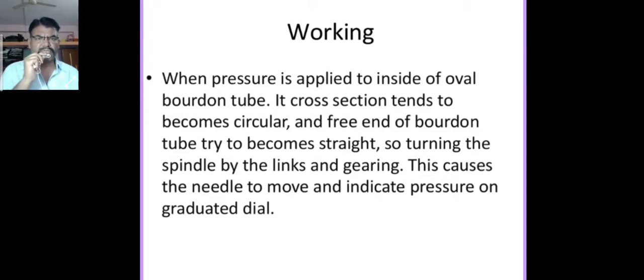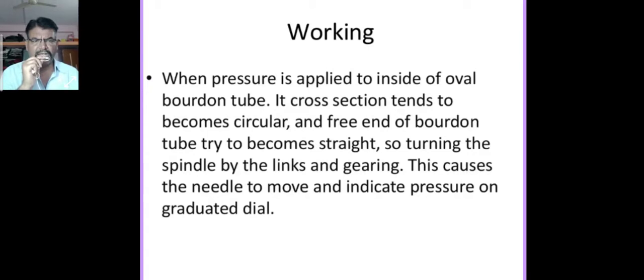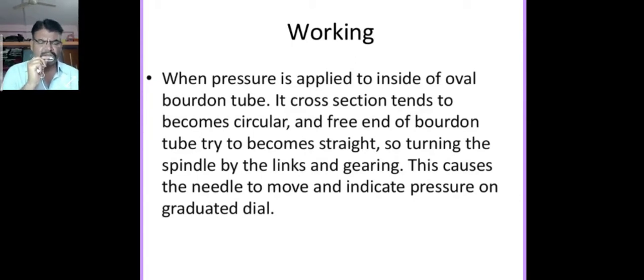When pressure is applied inside the oval Bourdon tube, its cross section tends to become circular and the free end of the Bourdon tube tries to straighten. This turns the spindle via the link and gearing, causing the needle to move and indicate pressure on the graduated dial.